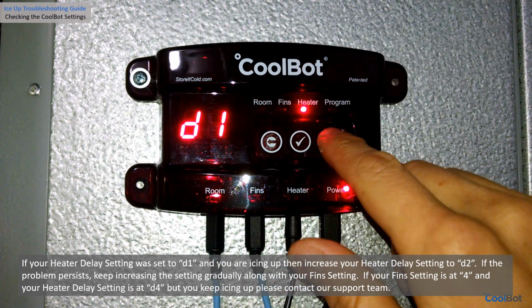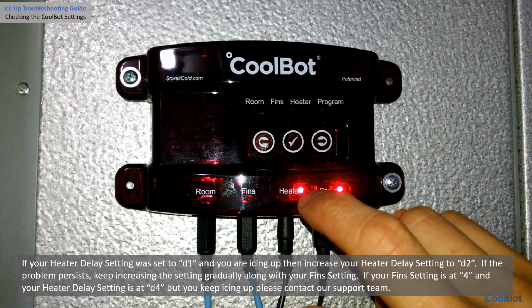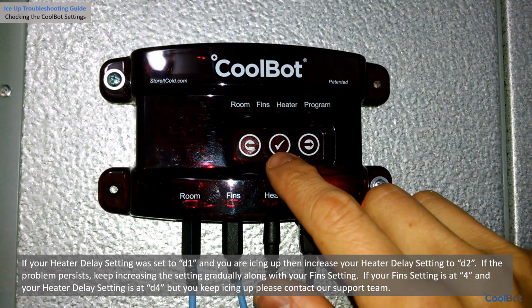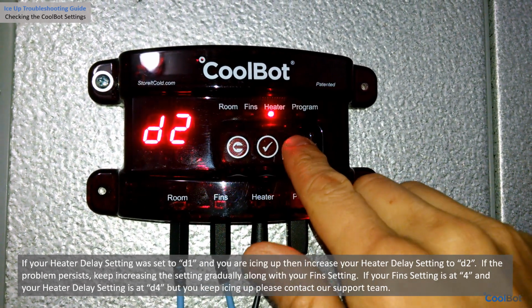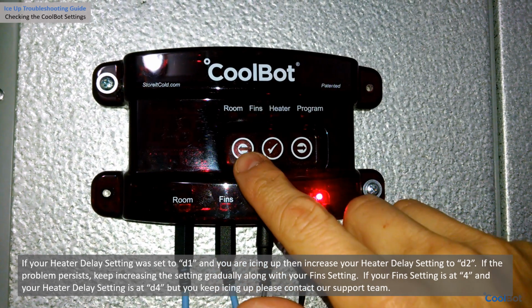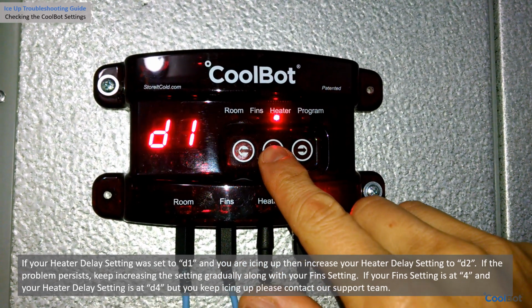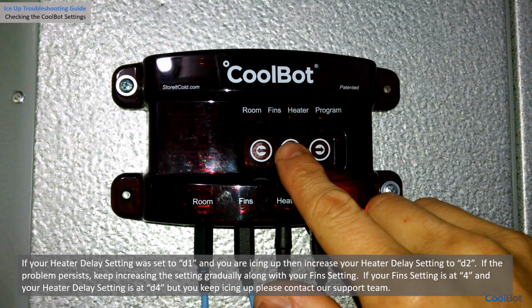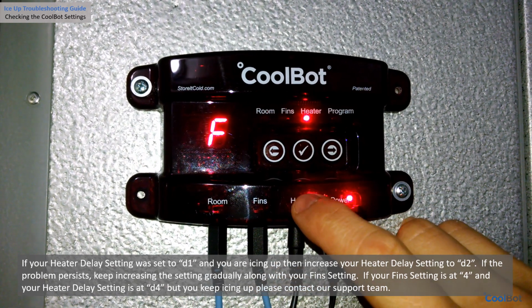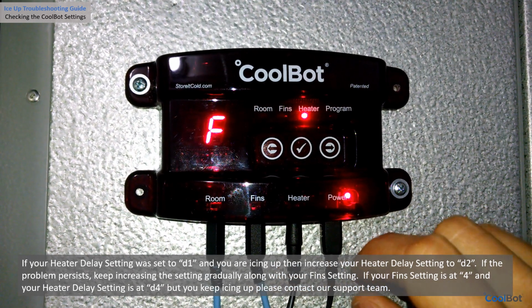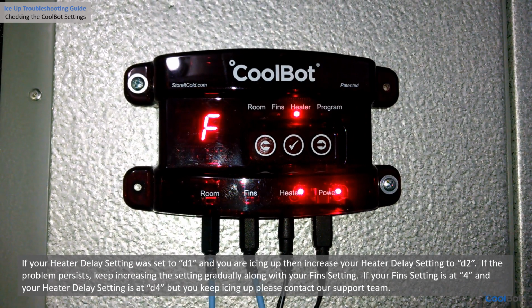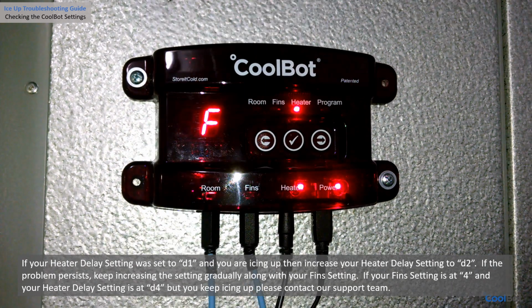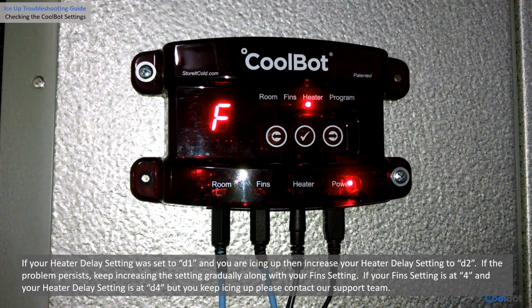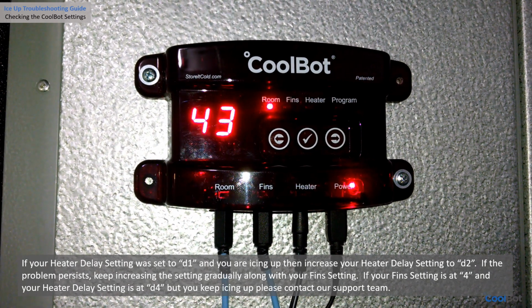The factory heater delay setting is D1. Most users find best results with a heater delay setting in between D1 and D4. Adjust with the arrows if necessary to the desired value. Press the check mark to save. Your CoolBot will go back to display F or C. After 30 seconds, it will jump back to the room position and display the current room temperature.